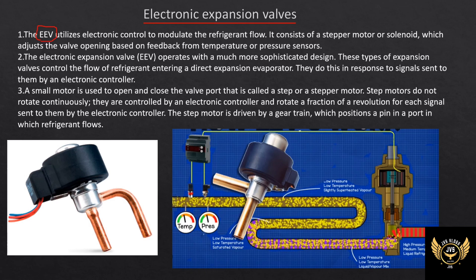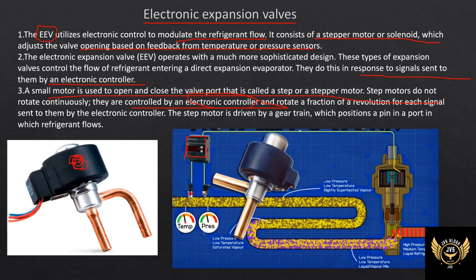Next, like the thermal expansion valve, we have the electronic expansion valve. This valve uses an algorithm and can operate automatically to meet temperature requirements. It uses a stepper motor driven by electronic control signals. The stepper motor controls the valve opening based on temperature and pressure sensing, regulating the amount of refrigerant. In the system there is a liquid line and a vapor line from the condenser through the expansion valve.